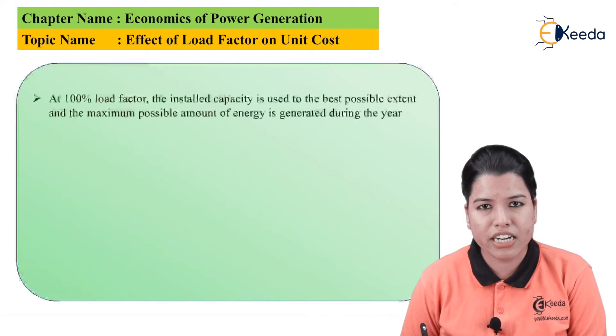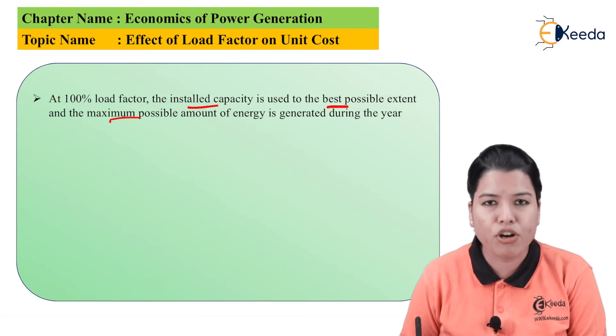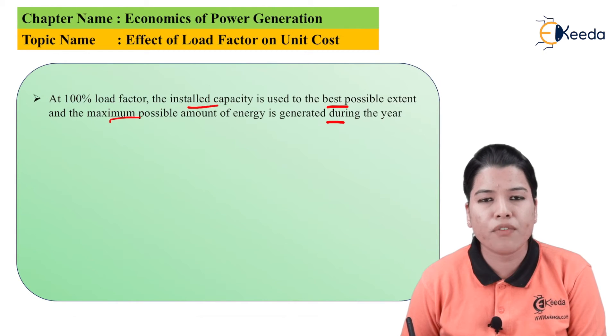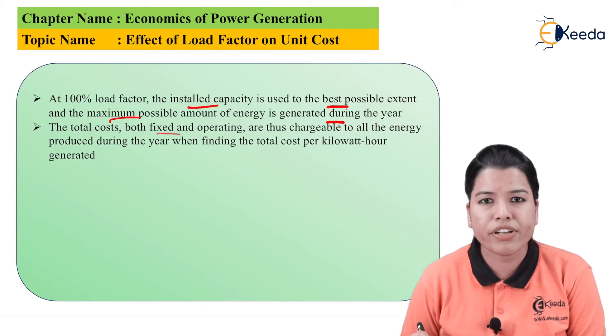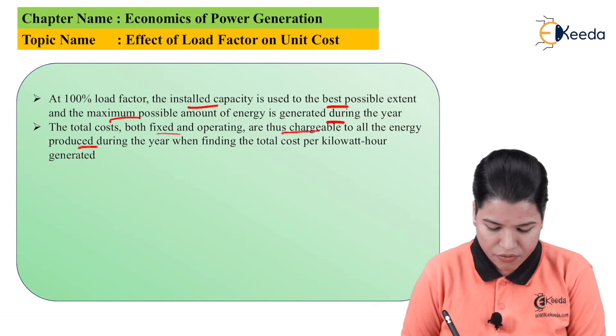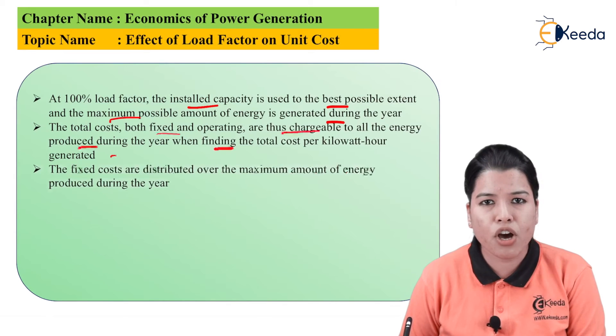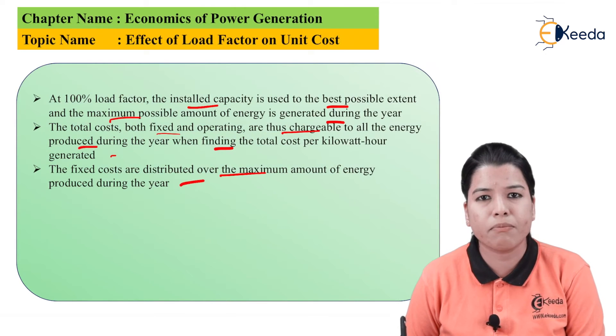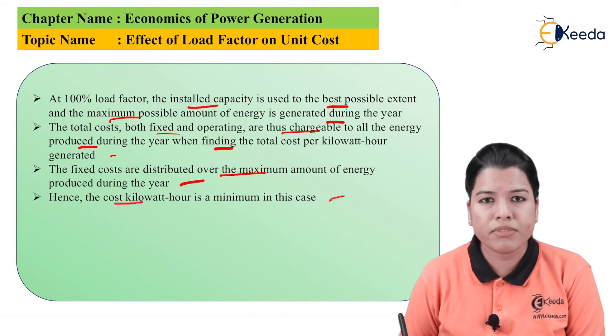Now if we consider a 100% load factor, then the installed capacity is used to the best possible extent and the maximum possible amount of energy is generated during the year. So when the load factor is 100%, the operation of the power plant is considered to be optimal. The total cost, that is both fixed cost as well as operating cost, are thus chargeable to all the energy produced during the year when finding the total cost per kilowatt-hour generated. Now the fixed cost gets distributed over the maximum amount of energy produced during the particular year, therefore the cost per kilowatt-hour is minimum in this particular case.